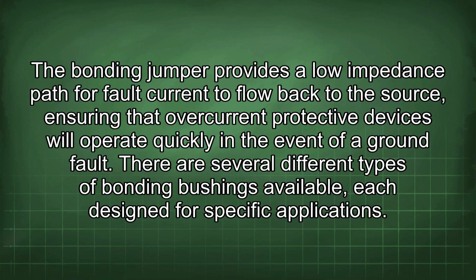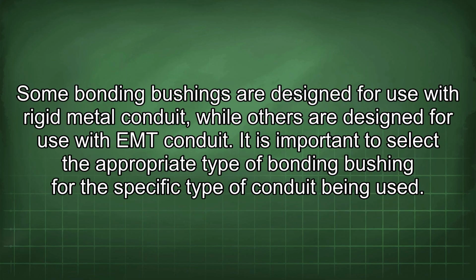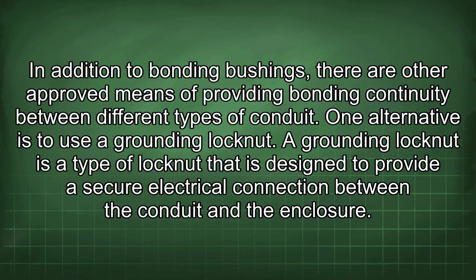There are several different types of bonding bushings available, each designed for specific applications. Some bonding bushings are designed for use with rigid metal conduit, while others are designed for use with EMT conduit. It is important to select the appropriate type of bonding bushing for the specific type of conduit being used. In addition to bonding bushings, there are other approved means of providing bonding continuity between different types of conduit. One alternative is to use a grounding lock nut. A grounding lock nut is a type of lock nut that is designed to provide a secure electrical connection between the conduit and the enclosure.